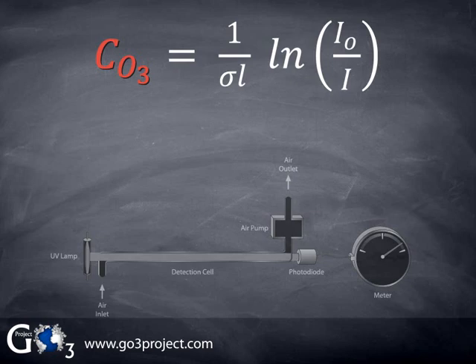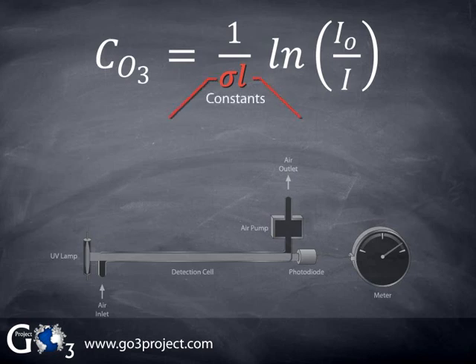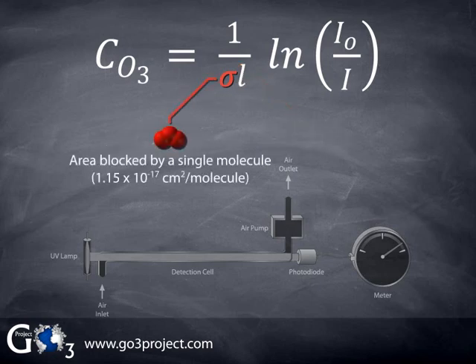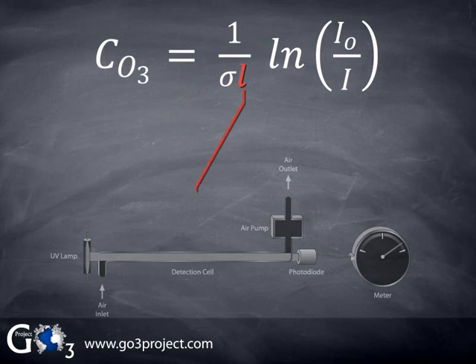Here, C sub-ozone is the concentration of ozone in units of molecules per cubic centimeter, or molecules per cc. Sigma and L are two constants that are fixed for our experiment. Sigma is a fundamental property of the ozone molecule called the absorption cross-section, and L is the length of the detection cell. Sigma, or the absorption cross-section, can be thought of as the effective area blocked by a single molecule of ozone.